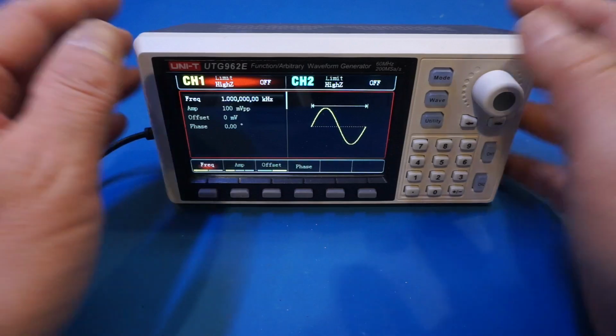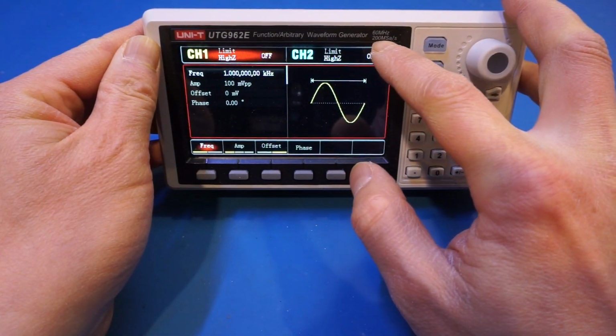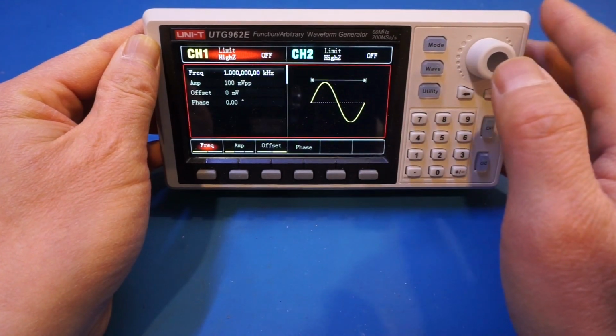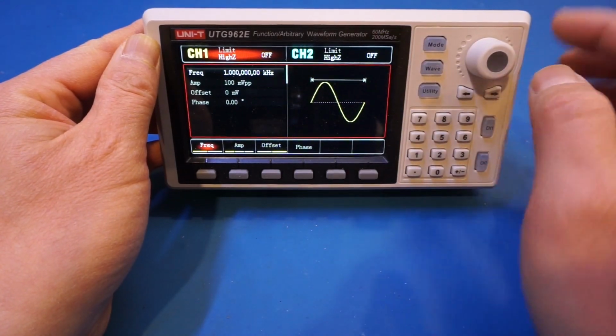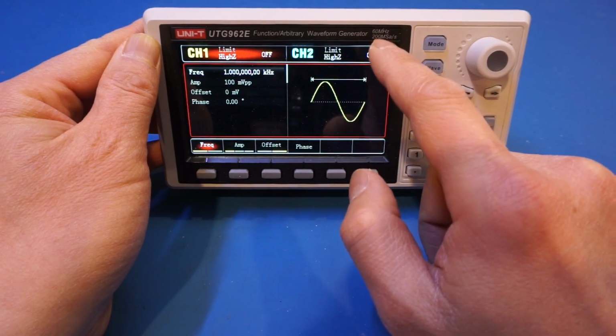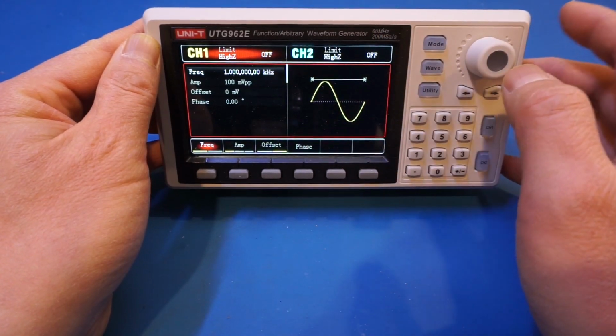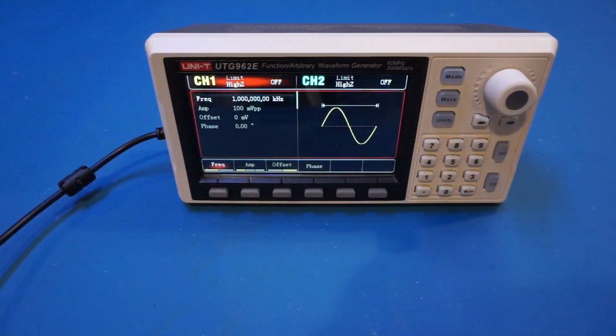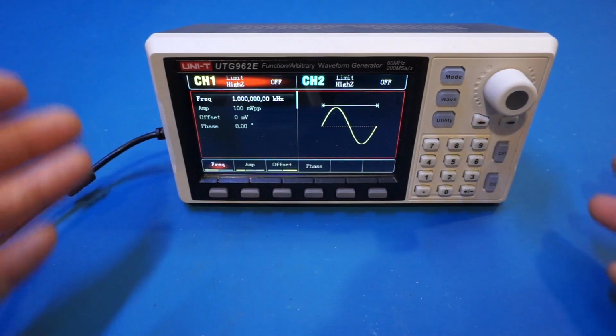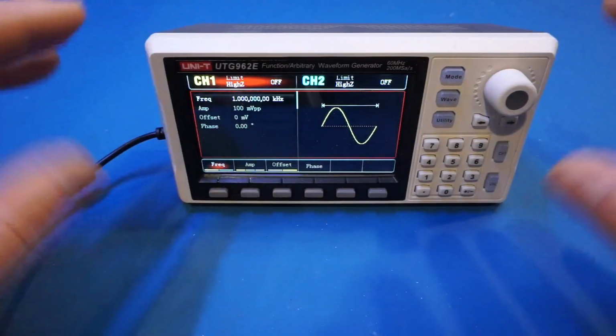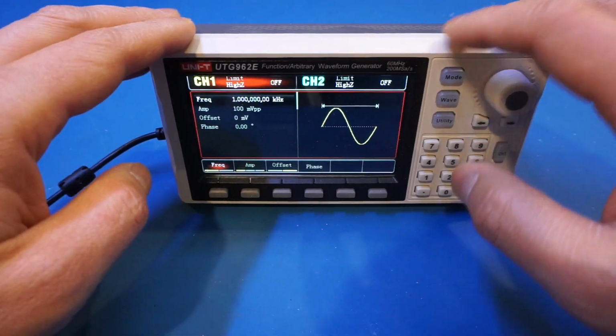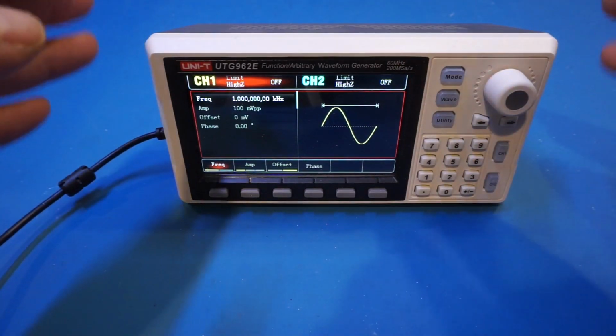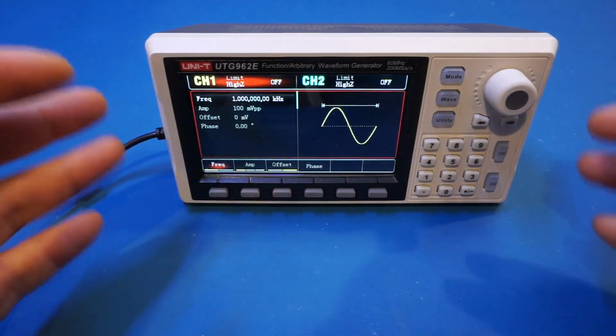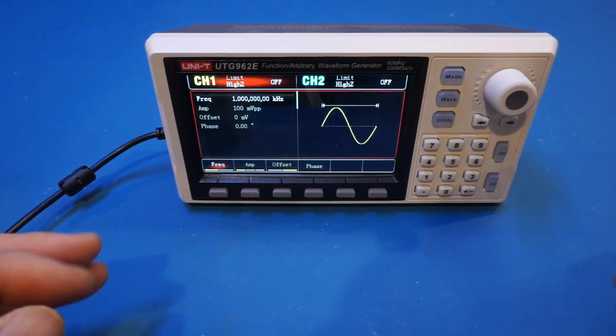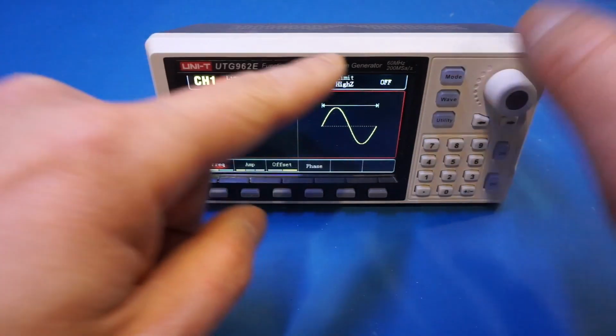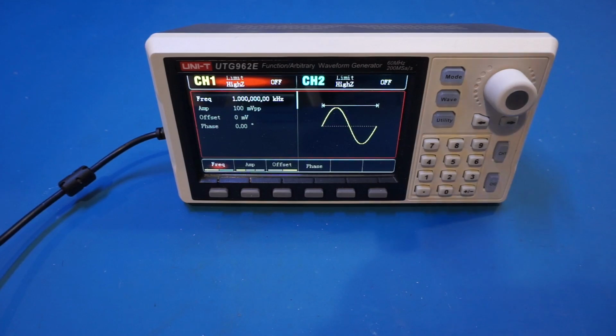The first limitation I wanted to point out is the maximum sampling rate of 200 megasamples per second. This unit has a maximum bandwidth of 60 MHz, so at this sampling rate, when you are outputting a 60 MHz signal, you are only going to have 3 samples per cycle. And your signal's fidelity is highly correlated with the number of samples in a specific period. Given the limitation of 200 megasamples per second, you're only going to achieve a very high output frequency on your simplest waveforms, such as sinusoidal. For all the complex waveforms, you cannot achieve that output frequency of 60 megahertz.